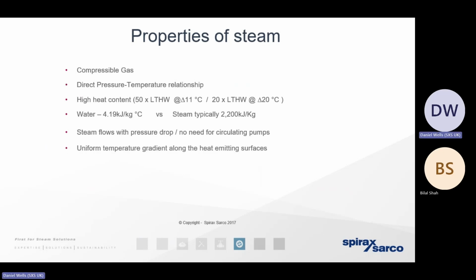Steam gives up its heat energy by spreading out across the heat transfer surface area very, very rapidly. When we depressurize the steam at the point of use in order to control the temperature, depressurizing the steam is going to expand. So it's going to spread across the entirety of the heat transfer surface area without leaving us with cold spots or striations like we commonly see with water-to-water heat exchangers. And because steam gives up its heat energy by condensing rather than by cooling down, the speed at which that high energy density can get into the process is about 3 times more rapid.